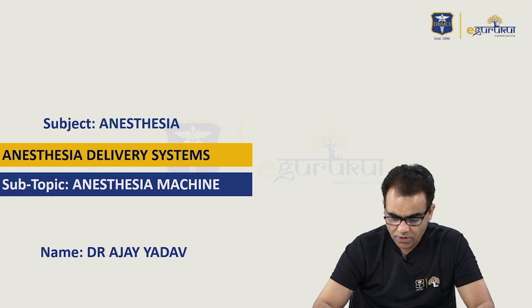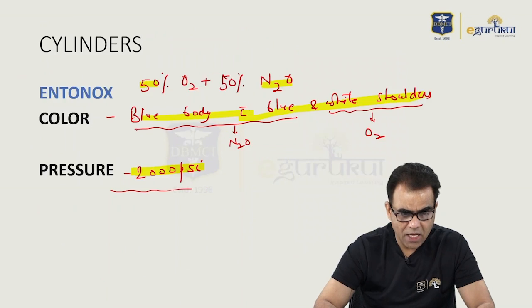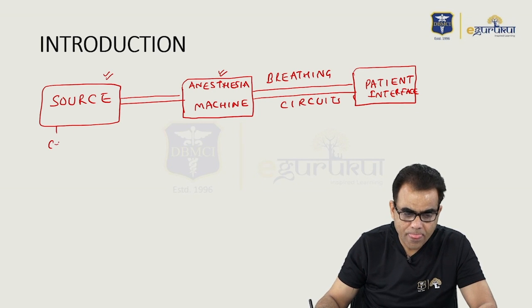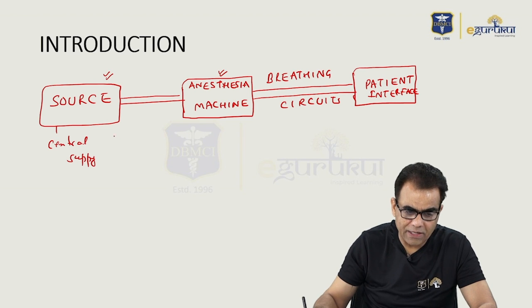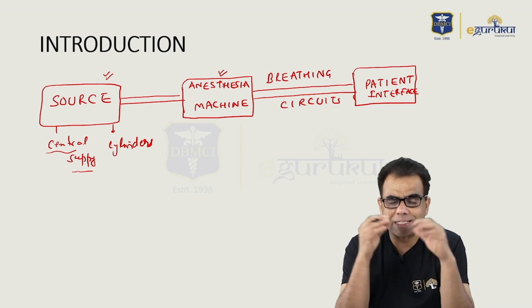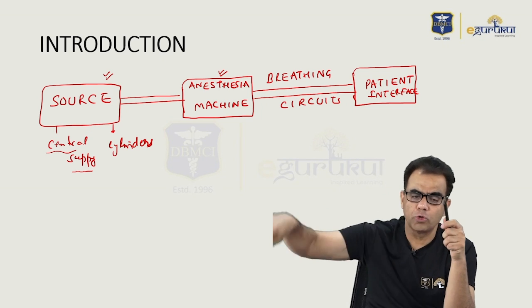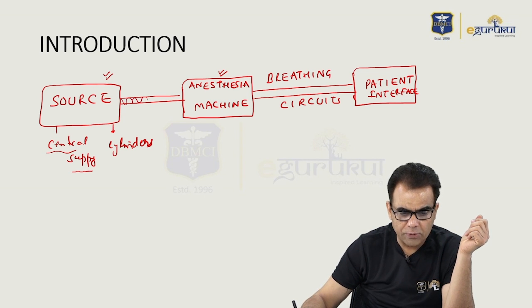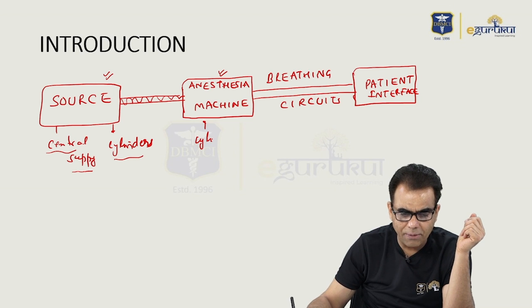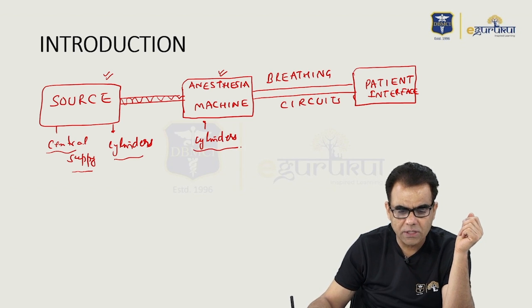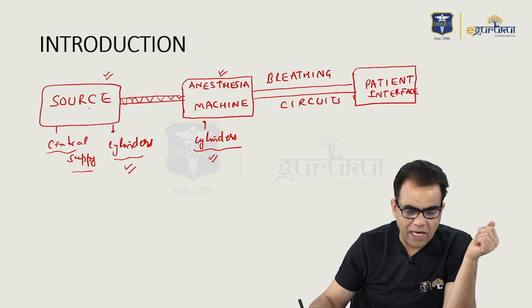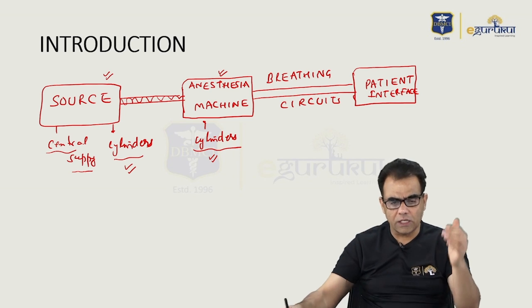Now, anesthesia machine. We have seen that sources of gases can be central supply or can be cylinders. With central supply, there will be a central supply room with a bank of cylinders, and through pipes, gases will be delivered to the anesthesia machine. Cylinders may be part of central supply or directly attached to the anesthesia machine. Either way, gases through central supply or through cylinders are delivered to the anesthesia machine.